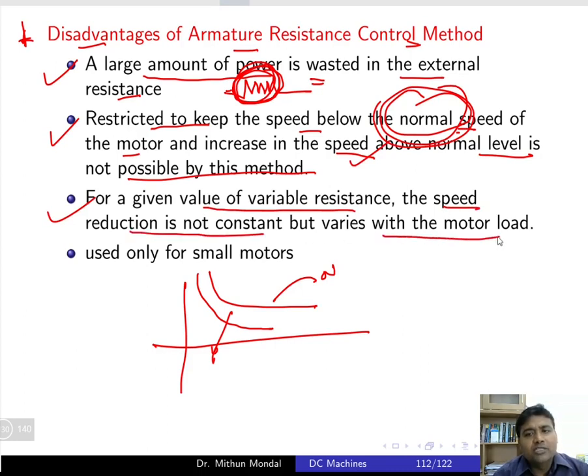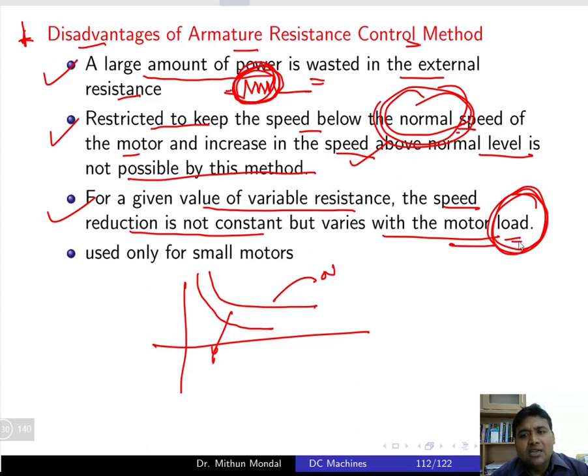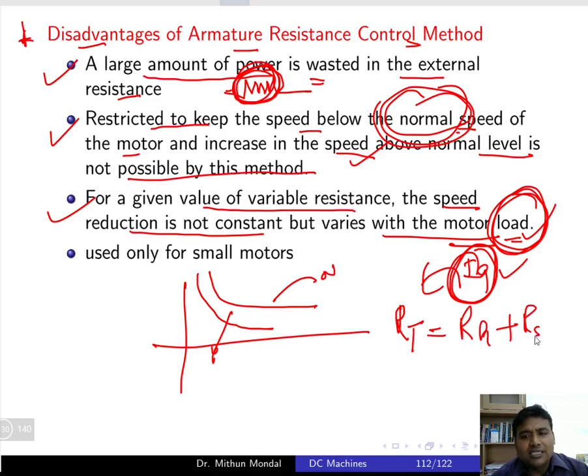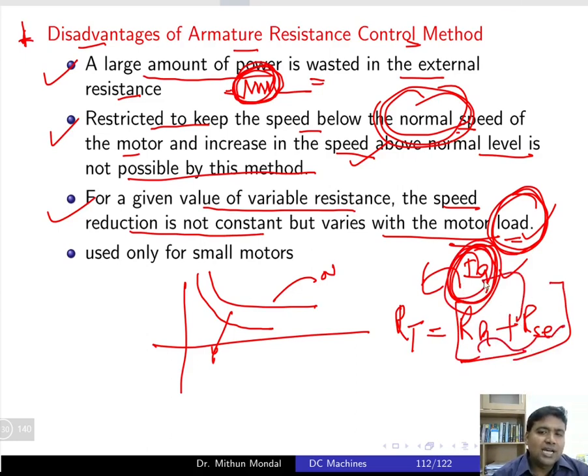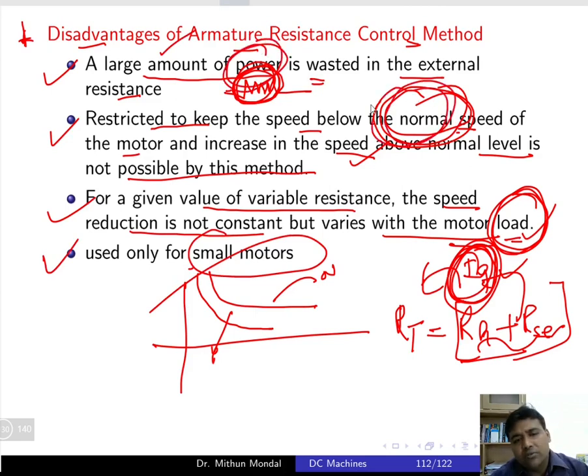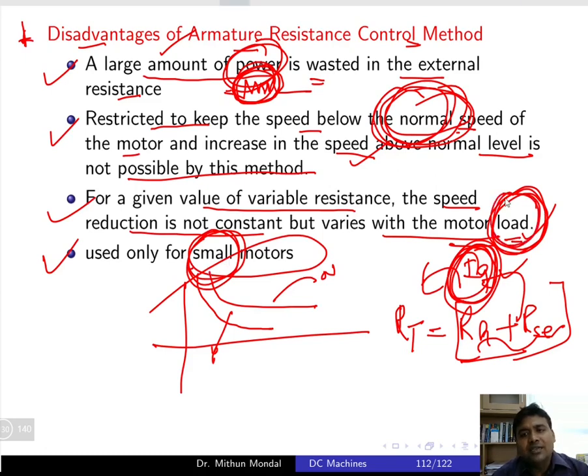Third disadvantage: for a given value of variable resistance, the speed reduction is not constant but varies with motor load. When the load changes, the armature current changes, which in turn affects the total resistance — total resistance equals armature resistance plus series resistance. This interaction makes speed control inconsistent. As a result, this method is used only for small motors, and the main disadvantages are power loss, inability to exceed normal speed, and load-dependent speed variation.